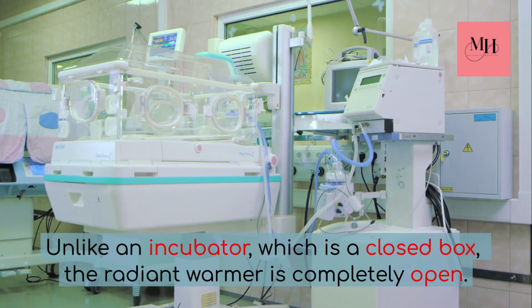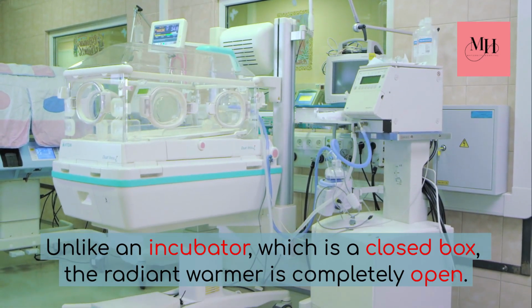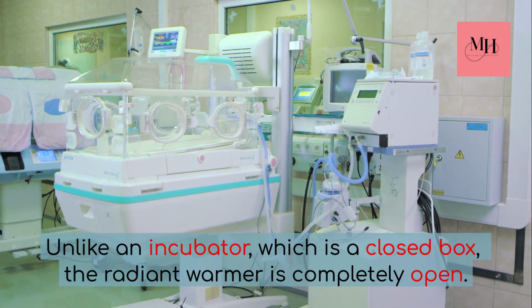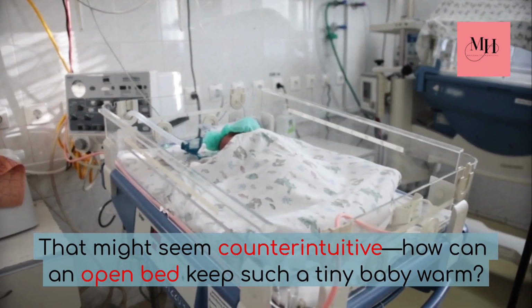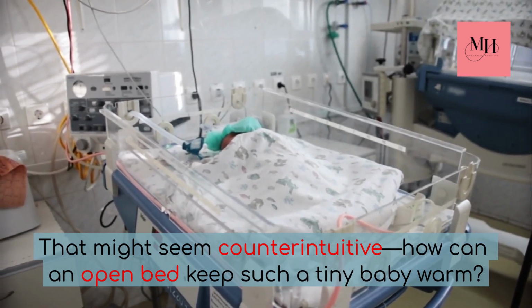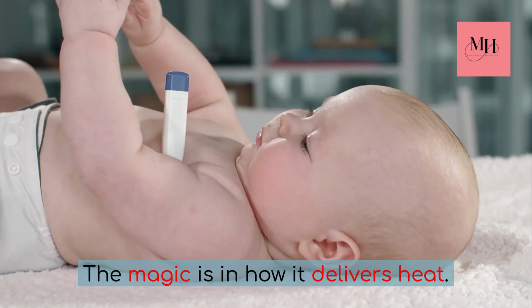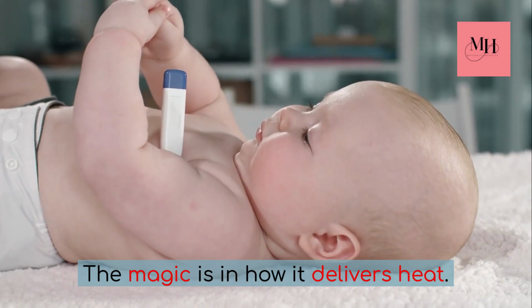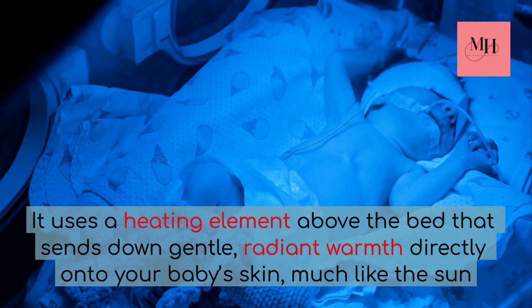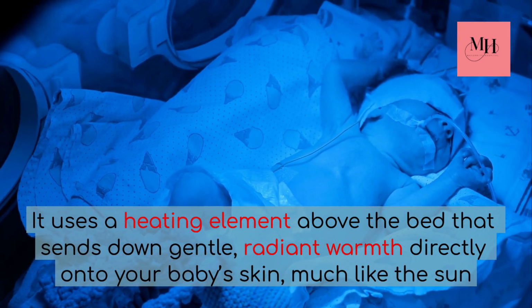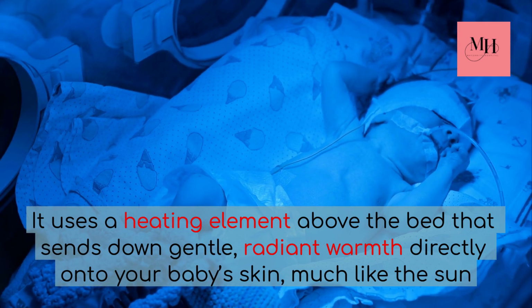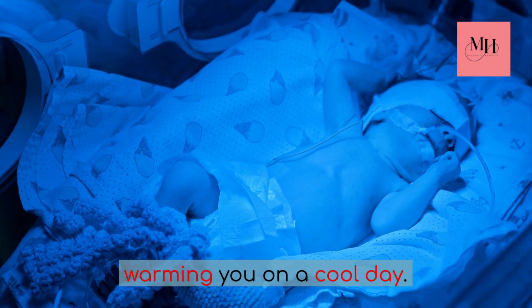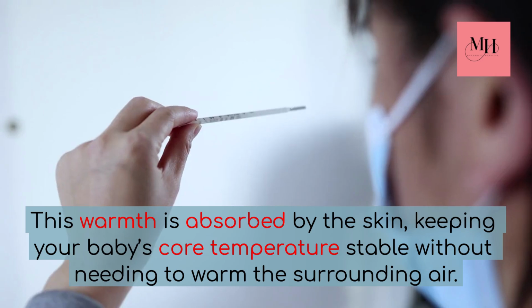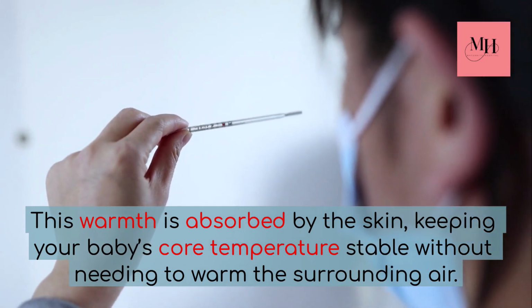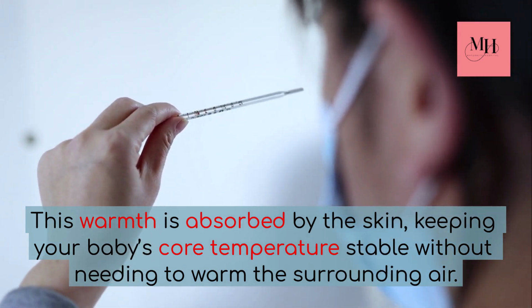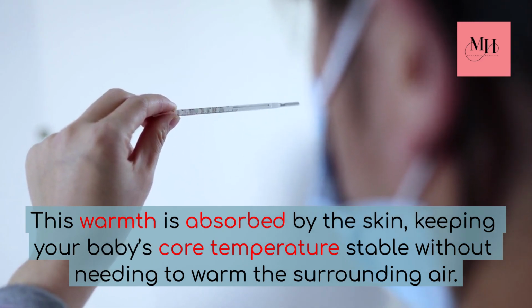Unlike an incubator, which is a closed box, the radiant warmer is completely open. That might seem counterintuitive. How can an open bed keep such a tiny baby warm? The magic is in how it delivers heat. It uses a heating element above the bed that sends down gentle, radiant warmth directly onto your baby's skin, much like the sun warming you on a cool day. This warmth is absorbed by the skin, keeping your baby's core temperature stable without needing to warm the surrounding air.